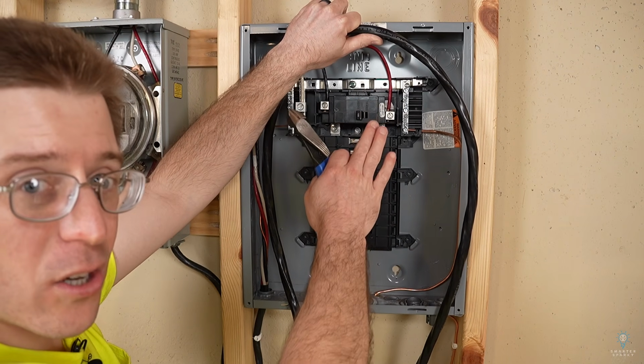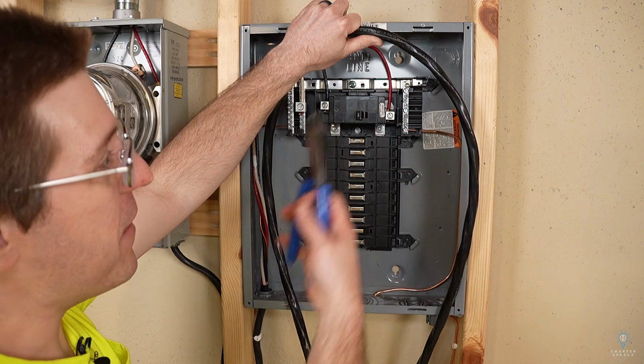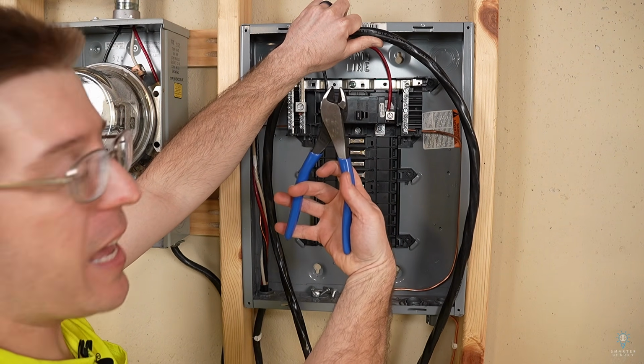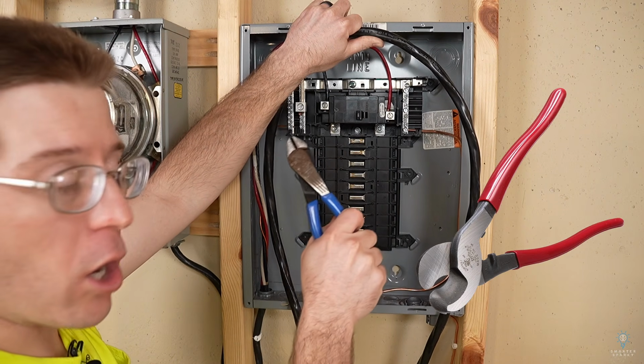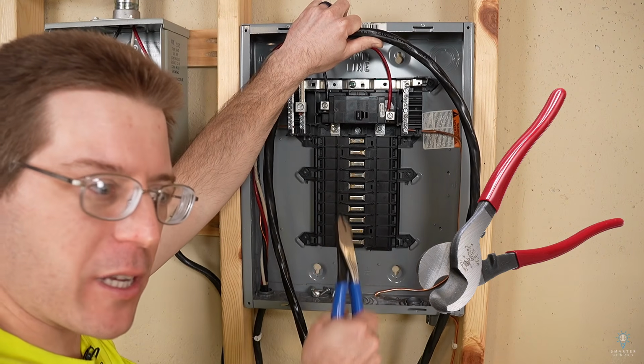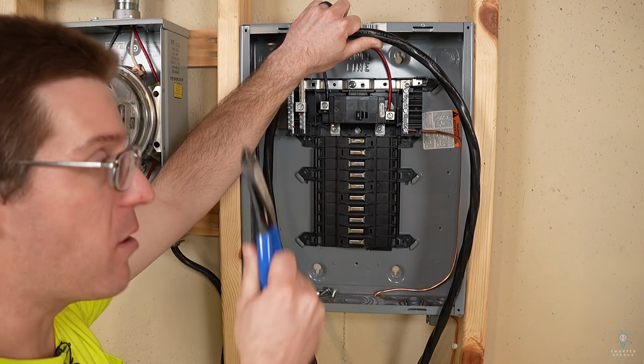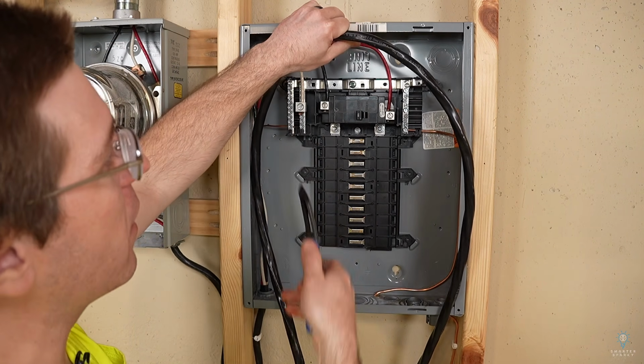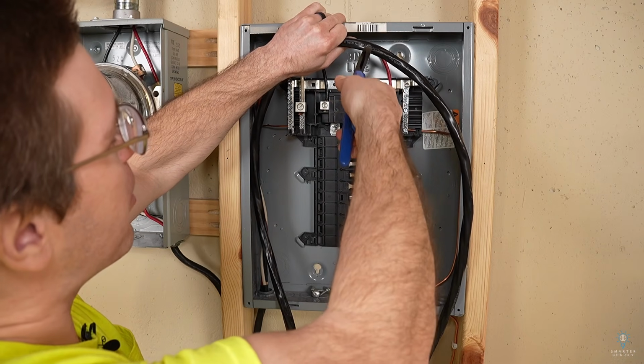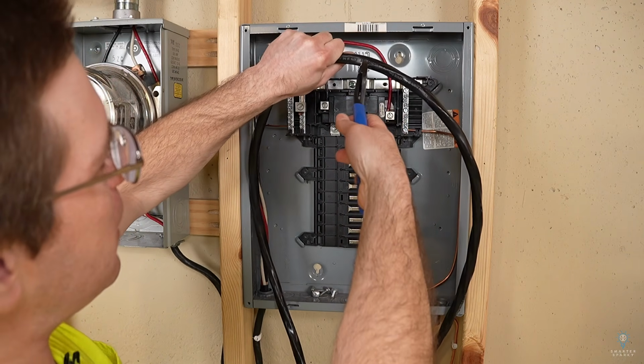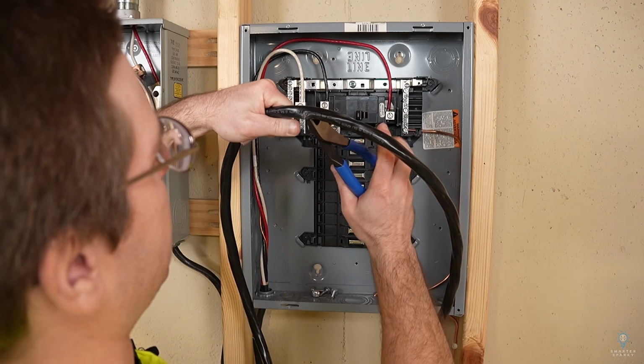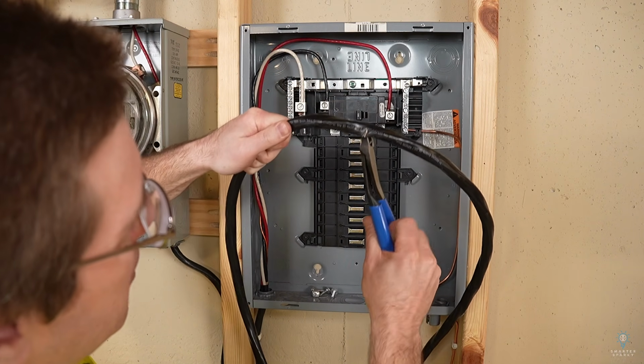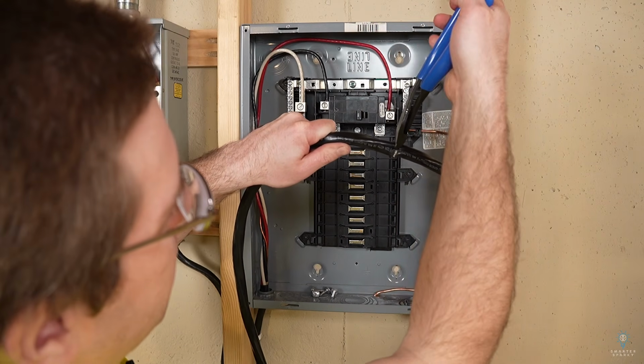Now cutting this larger wire can actually get a little tricky. In this case, I'm just gonna use a pair of diagonal cutters. Ideally, you'd have a larger cable cutter. My cable cutter is not available at the moment, so I'm gonna use what I have. I've got a diagonal cutters. So basically, I'm just gonna come in here and I'm gonna cut each wire individually. And like I said, this is very tricky because these wires are so much bigger, and it's even trickier to hold it up to the camera.